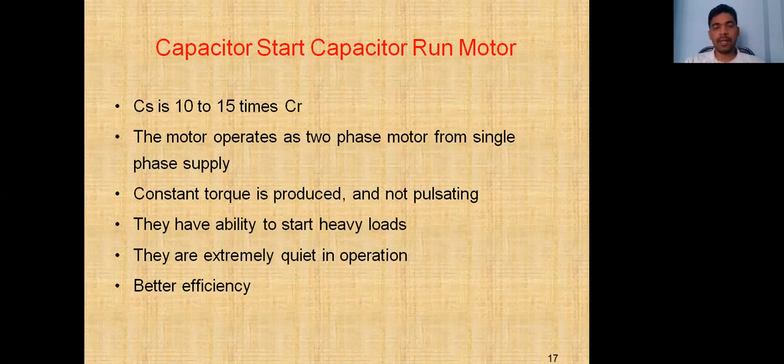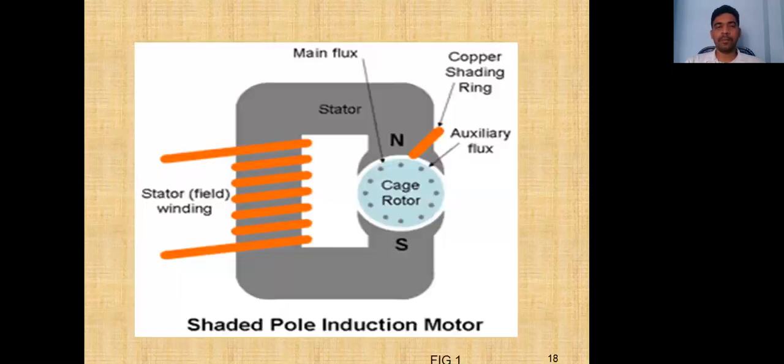They are extremely quiet in operation and it has better efficiency. Power factor is from 0.8 to 0.95. Because of the permanent capacitor, its power factor is improved.